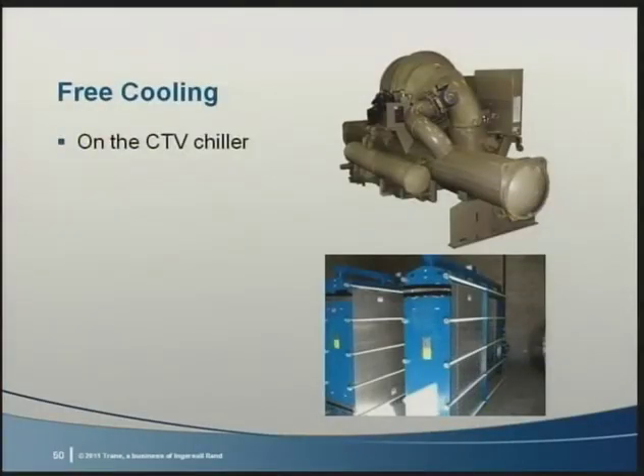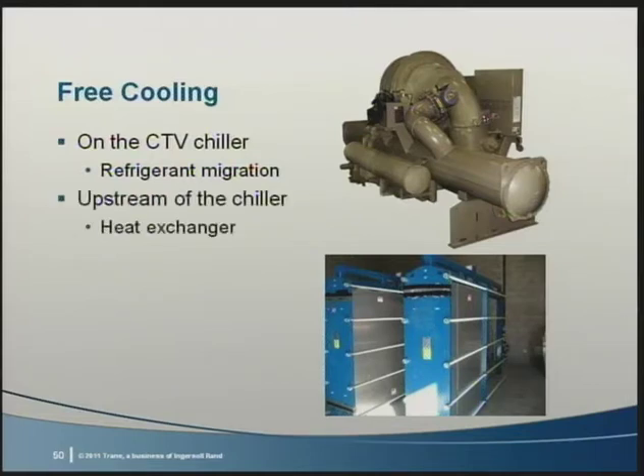One method for reducing energy consumption is to add free cooling. This may be through the addition of a heat exchanger, a plate and frame water side economizer, or by modifying the centrifugal chiller to add refrigerant migration free cooling. For this to provide savings, the ambient wet bulb temperature must be low enough. When this is available, the heat exchanger transfers heat from the returned chilled water to the water returning from the cooling tower. This can either be used instead of operating a chiller or to pre-cool the water to an operating chiller. Both methods will reduce energy use.